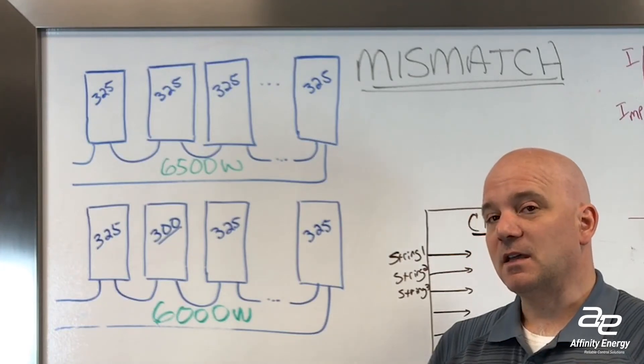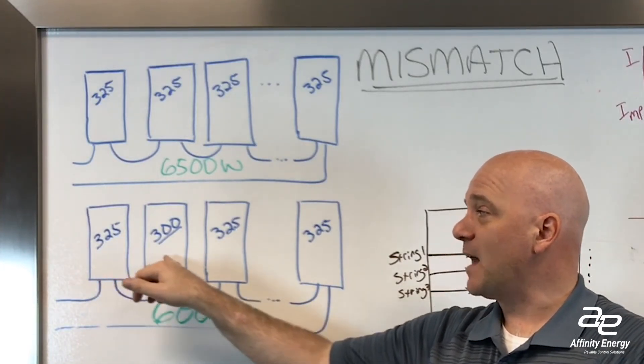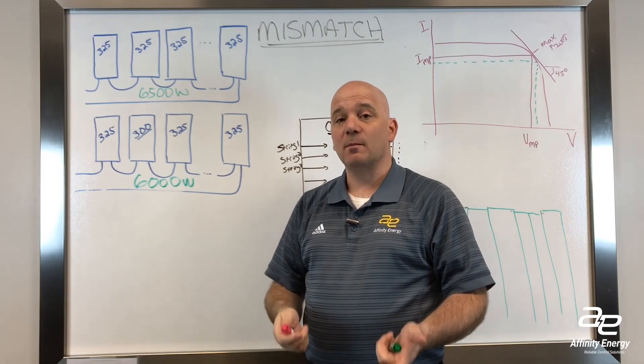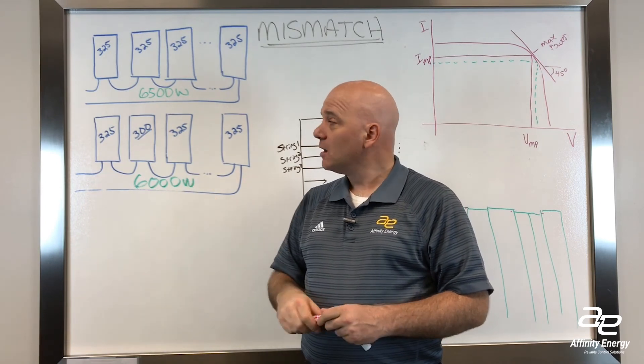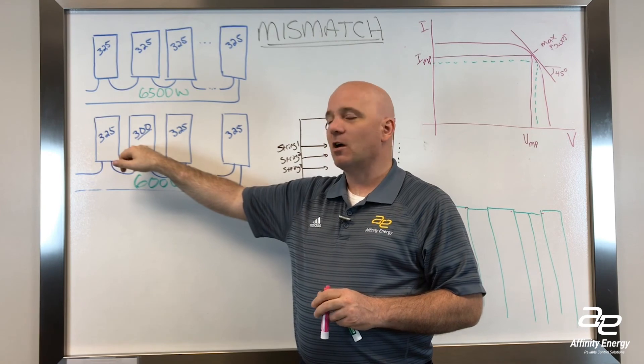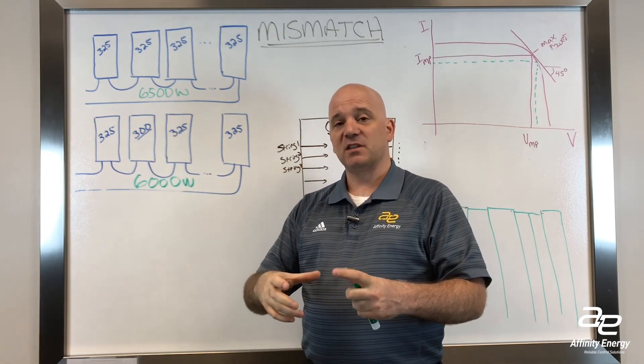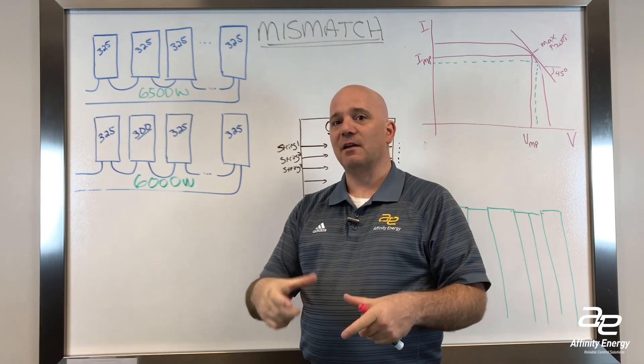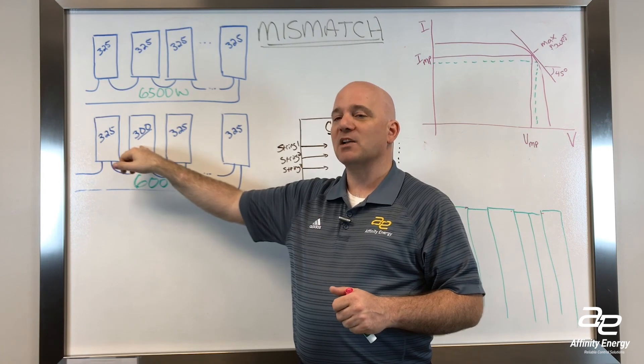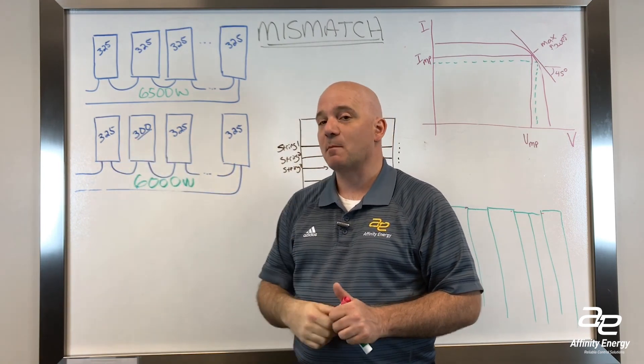The other thing that isn't obvious, but you might pick up on here, is that module mismatch going from 325 to 300 back to 325 is a rather dramatic difference. But a module that's underperforming could be caused by something as small as a cracked module, some hydraulic fluid left over from the construction process, or a soiling condition affecting one module amongst the string — and that will have the same effect as having a mismatched module.